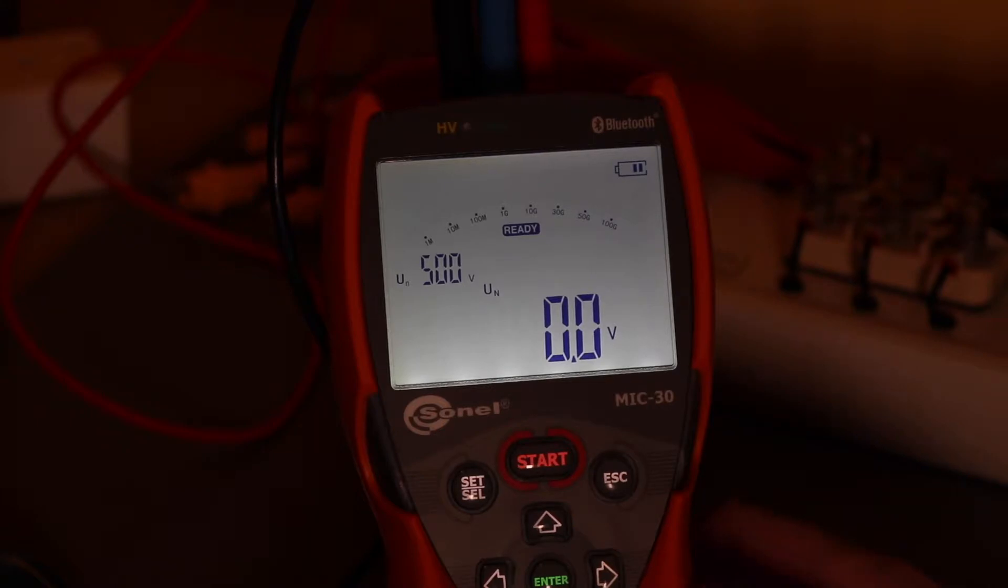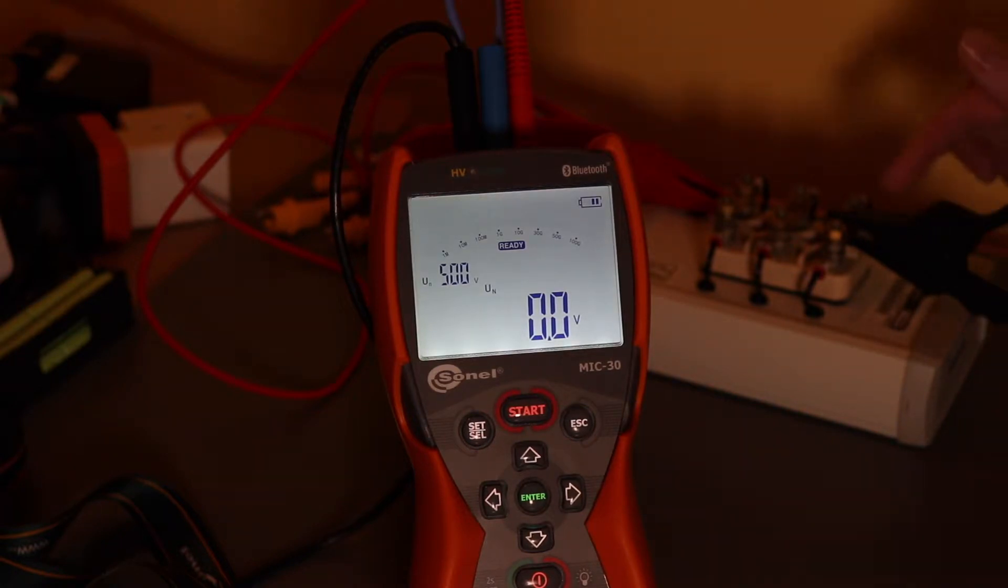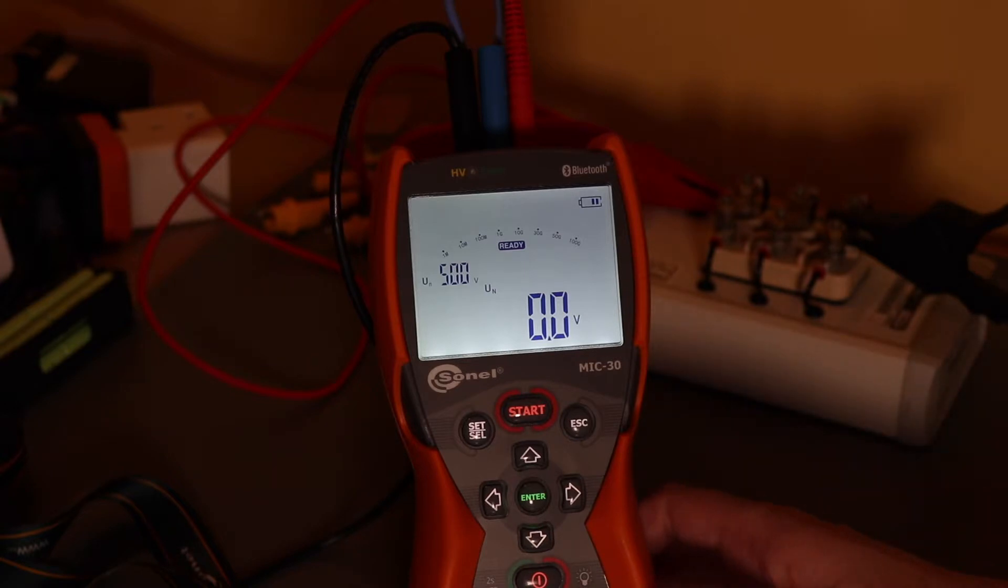I'm set up for a 500 volt test. I'm connected up over here to the winding simulator. This is a standard polarisation index test. So I've got one lead on one of the windings. The other lead is on the back here on the earth stud. And because I have a guard terminal on this tester, I can select the shielded test lead and link them two out to avoid any leakage between the leads.